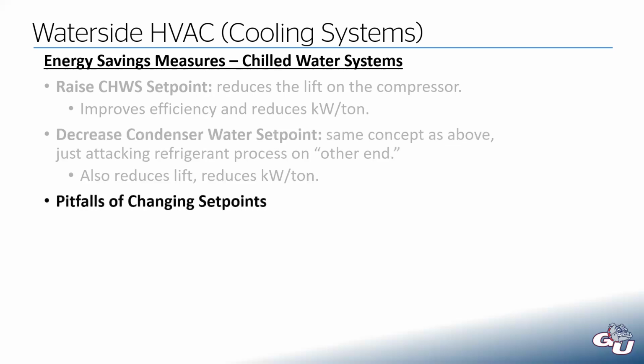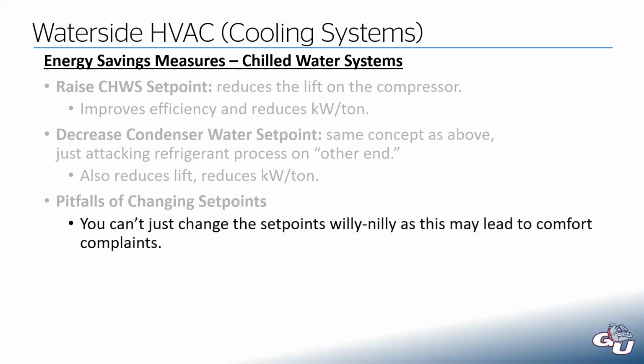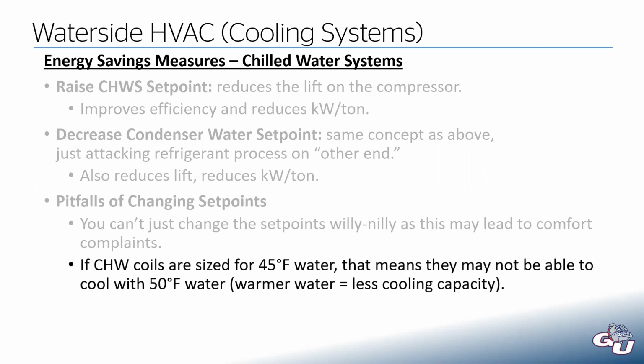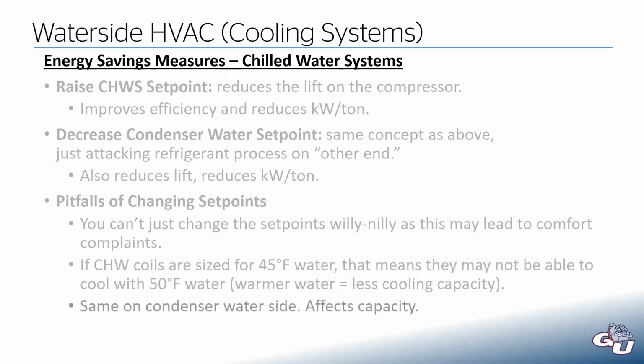But the thing you need to watch out for, anytime you're changing these set points, you can't just go in and say, well, you're supplying your chilled water at 45 degrees, we're just going to raise that to 50. You can't just do that. If all of your coils are sized for 45-degree water, they might not be able to cool properly with 50-degree water. If you have warmer chilled water, that means you have less cooling capacity. And the same thing occurs on the condenser water side. Changing these set points messes with the cooling capacity of the system.